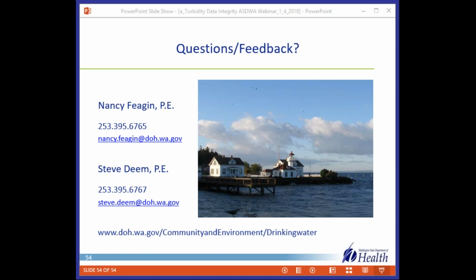Do you have recommendations on how plants should set up their SCADA systems to differentiate between valid turbidity readings and those taken during other time periods, like during filter backwashes or filter to waste time periods, etc.? Yeah, so you definitely need that, and often having the valve position shown on SCADA along with the turbidity display will allow you to visually see that. I'm not a SCADA expert by any means, but you definitely need to be able to exclude those times when the filter is not actually in service.